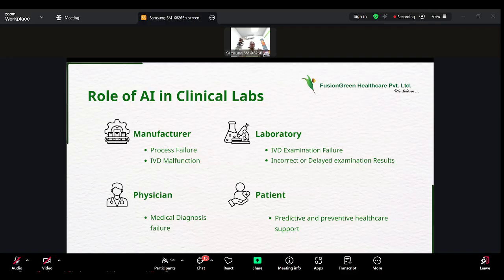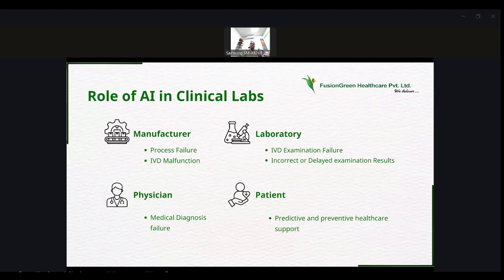Right now, what we are doing is manufacturing, and at the end of the stage, we go for the QC test. Then only we come to know there is a problem if the QC is not passing. Then they will go and check whether it's a mechanical failure, a fluidics failure, or an electronic failure. Then only will we be able to know. Because of AI in manufacturing, depending upon the stage 1, stage 2, stage 3 process itself, we can identify defective things and rectify them in the initial phase itself, and we don't need to wait until the QC checks. It is common for instruments as well as for reagents, calibrators, and controls.